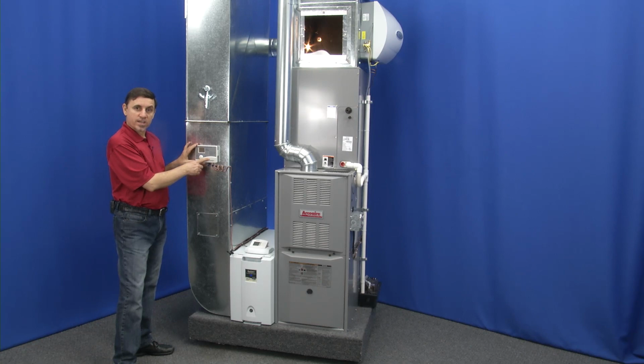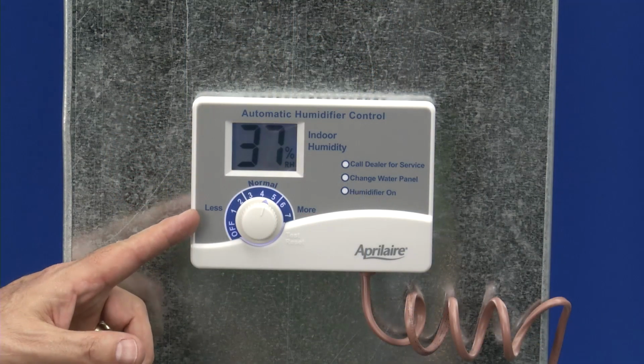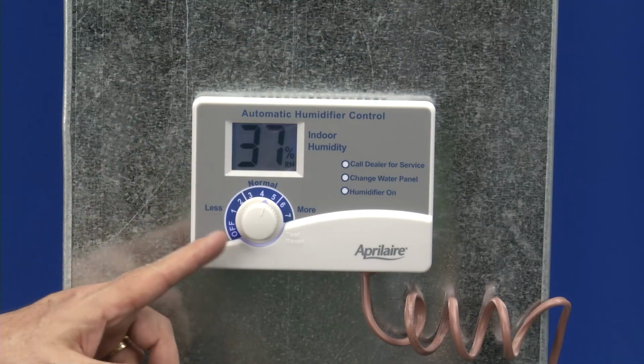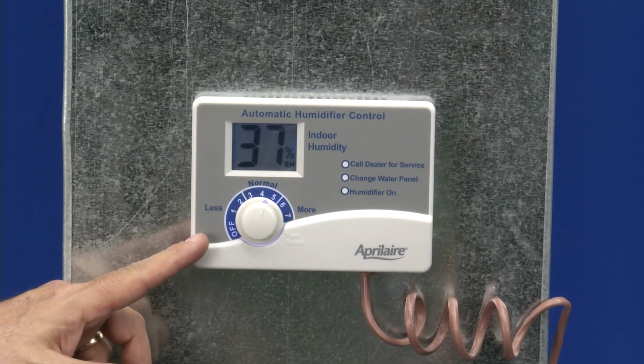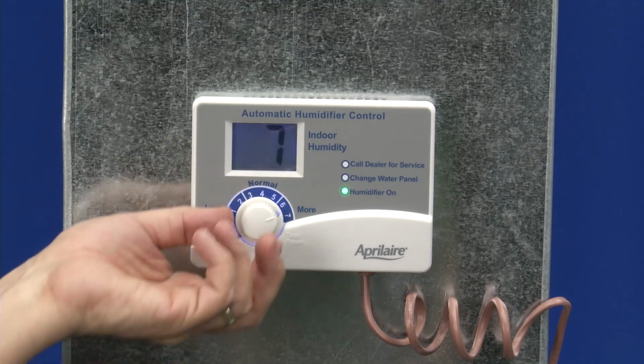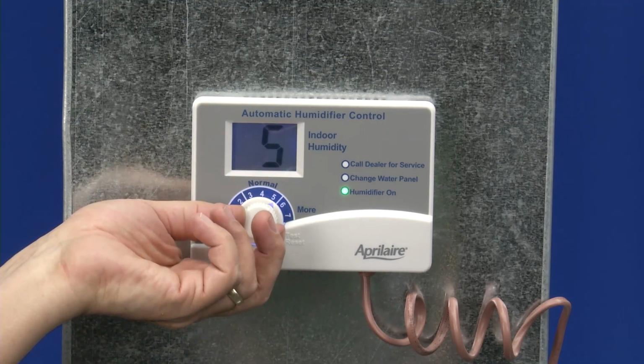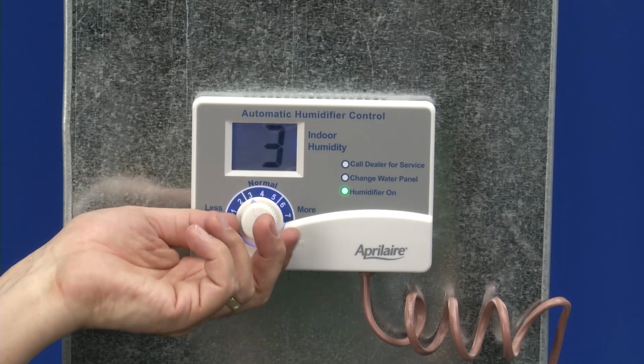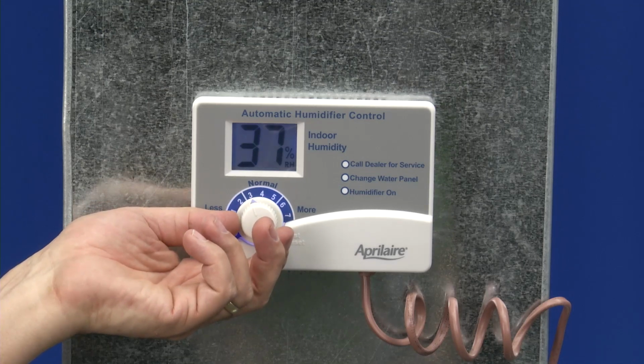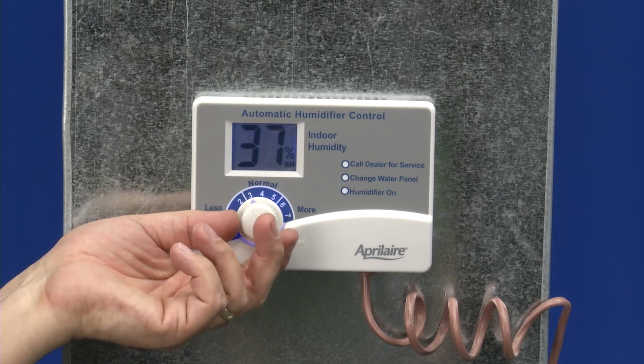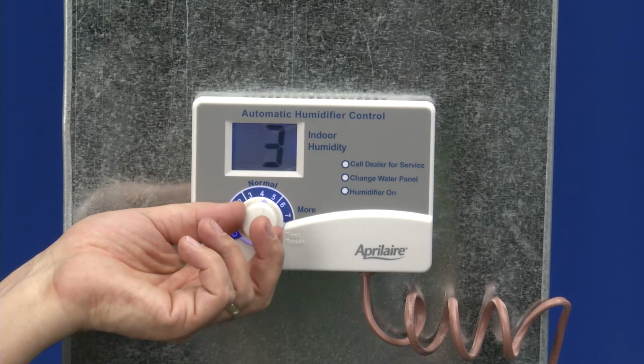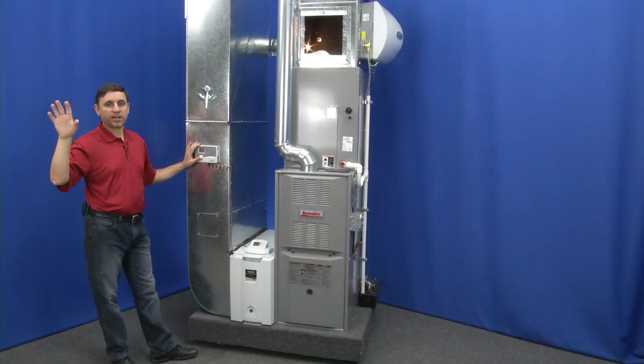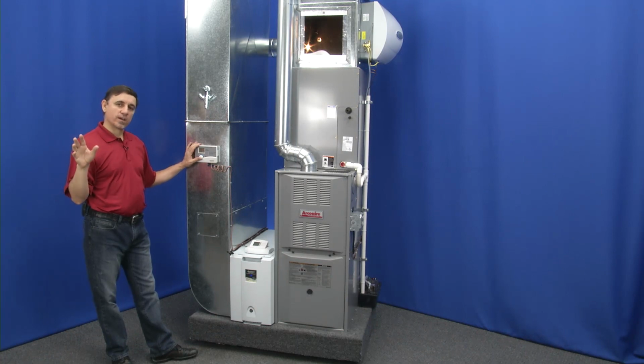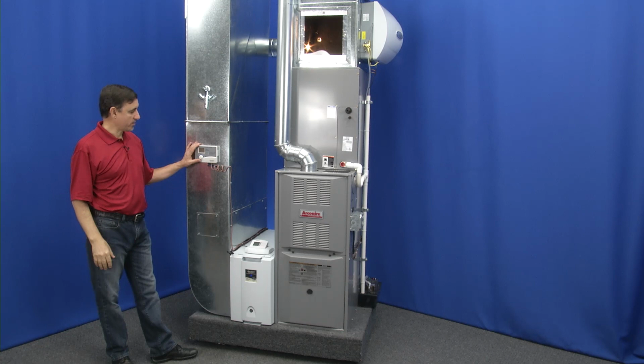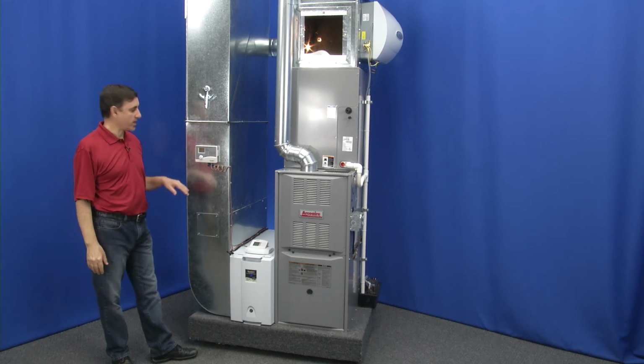This happens to be a humidistat. This can be mounted on the return air duct, which is the most common location you'll find these humidistats. This one is a digital one. There are mechanical ones as well. They are, again, most often mounted on the return air duct, although sometimes, certain models at least, can be mounted inside the home. And when they're done that way, they are often very closely mounted to the thermostat, like within a foot or two of the thermostat.